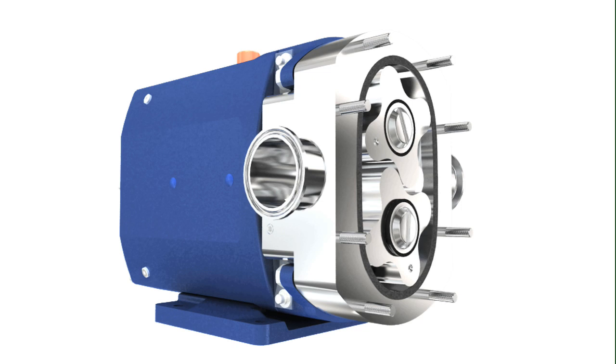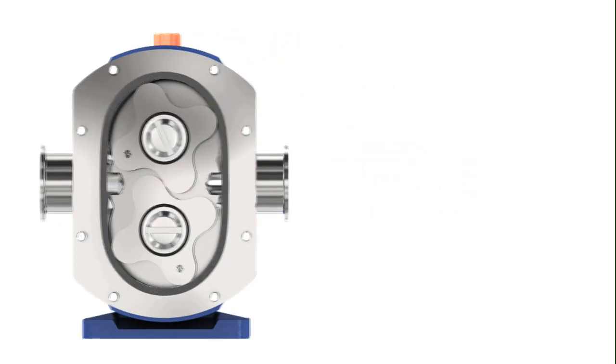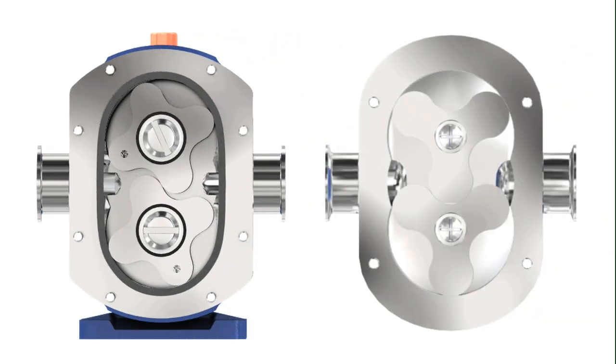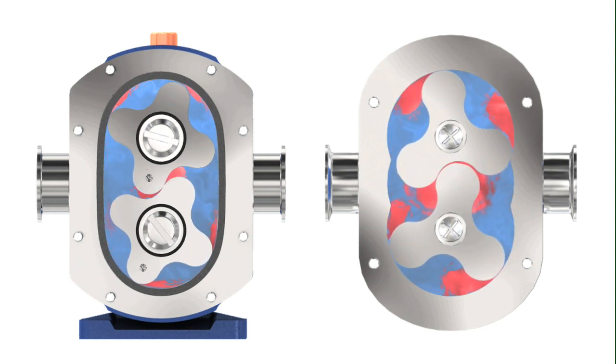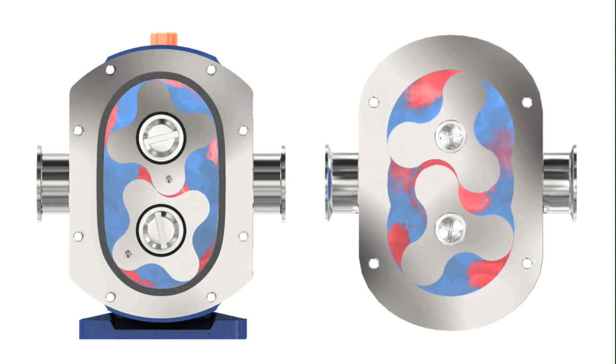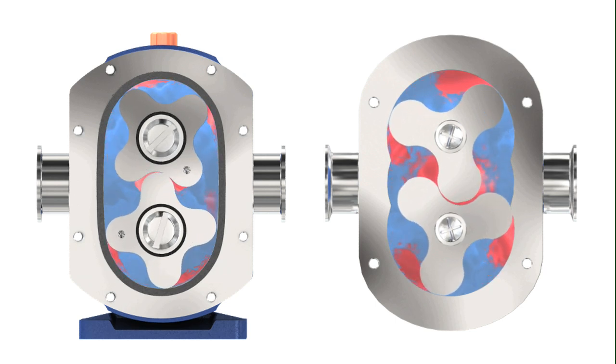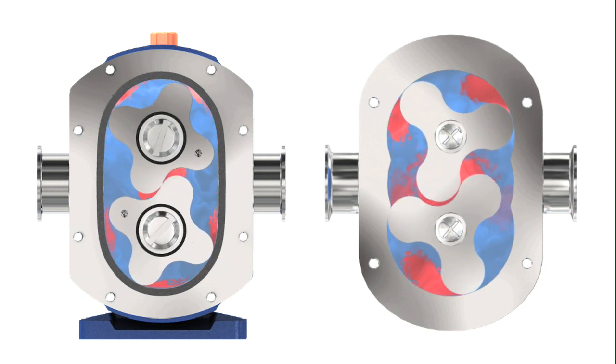To ensure exceptional product handling of shear-sensitive liquids, the SX incorporates close clearances to minimize product slip. The four-lobe geometry reduces shear of the liquid as it enters and exits the lobe cavities and also reduces pulsation.